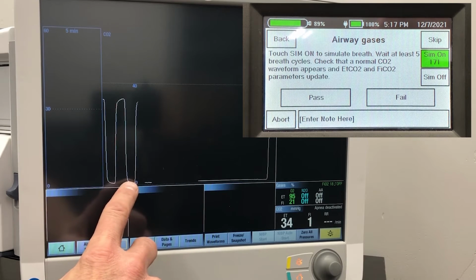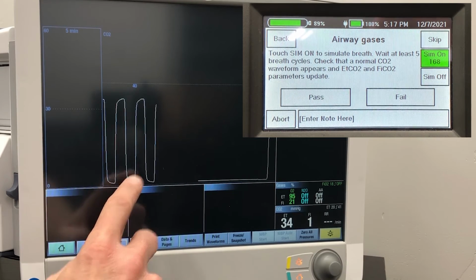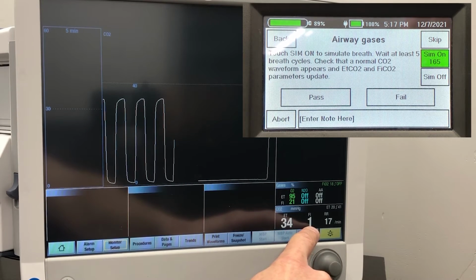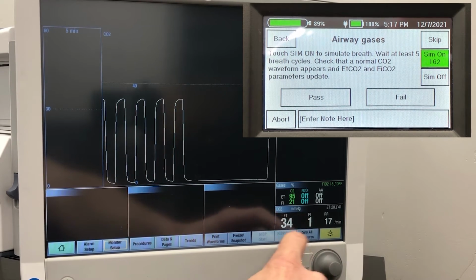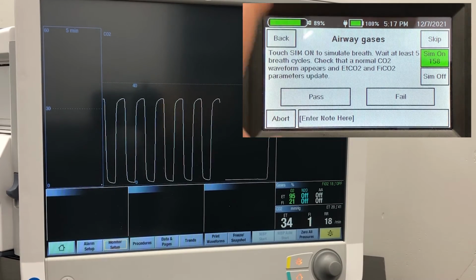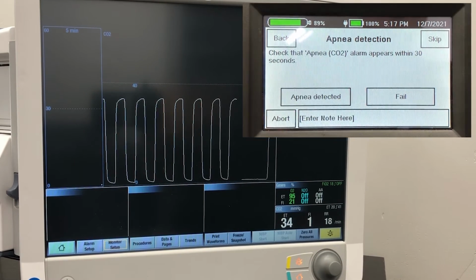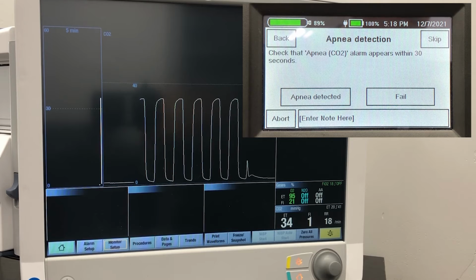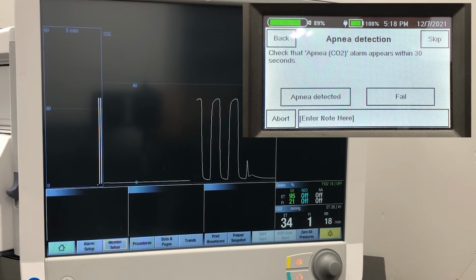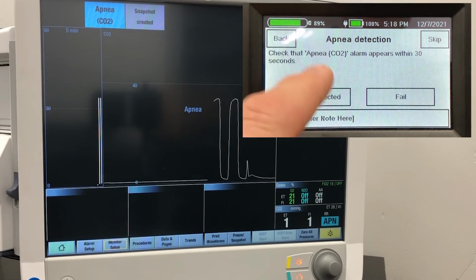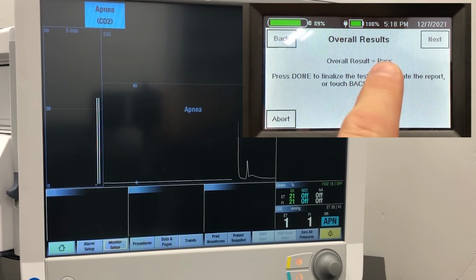You can see a waveform here that looks a lot like a capnogram. We just verified that end-tidal and FiCO2 update and give us values. So that's a passing result. Now that the SmartTank has stopped simulating breath, we should get an apnea message or alarm on the monitor. This is an important alert because obviously it tells the clinician that their patient has stopped breathing. So it's always an important one to test. There it is. So apnea is detected. So the overall result is pass.